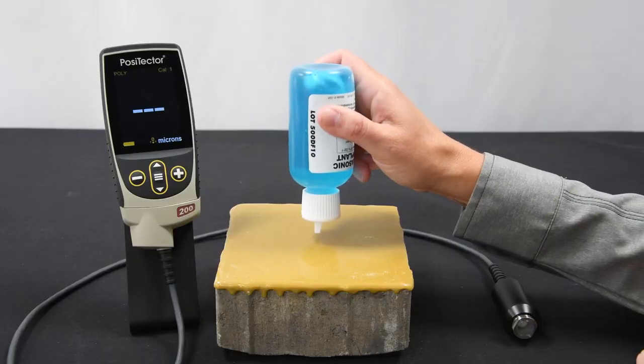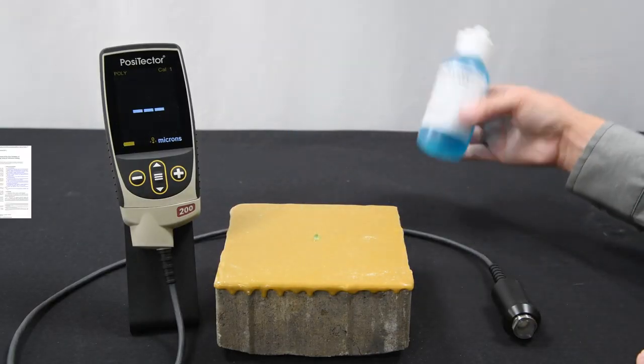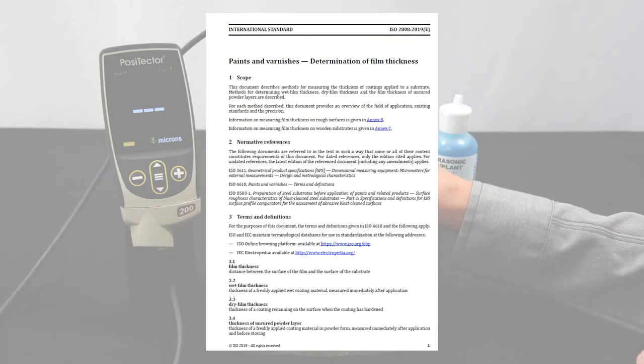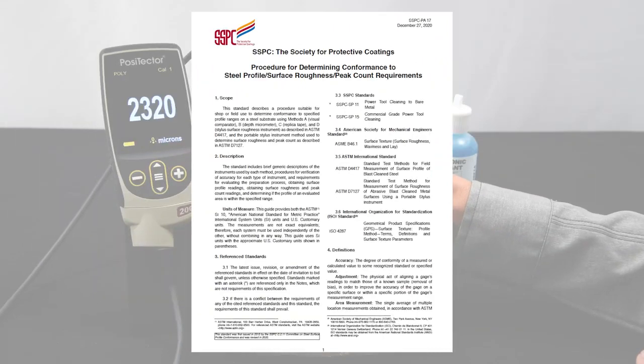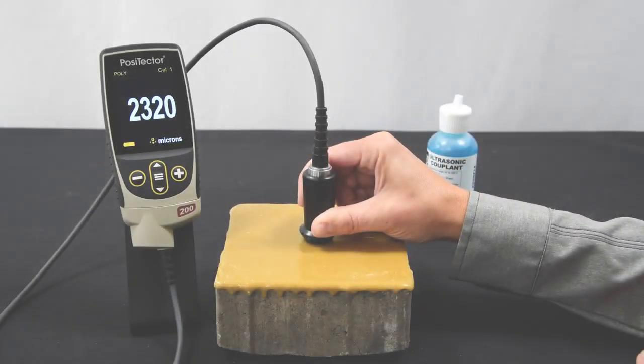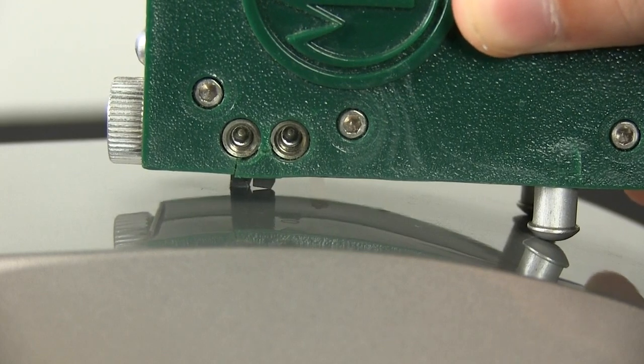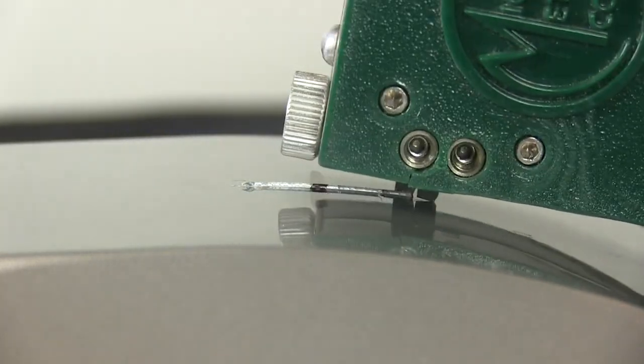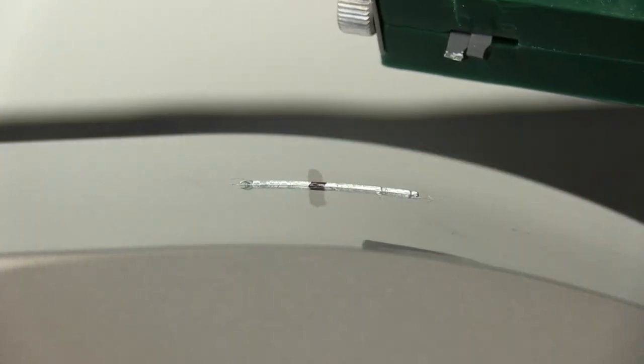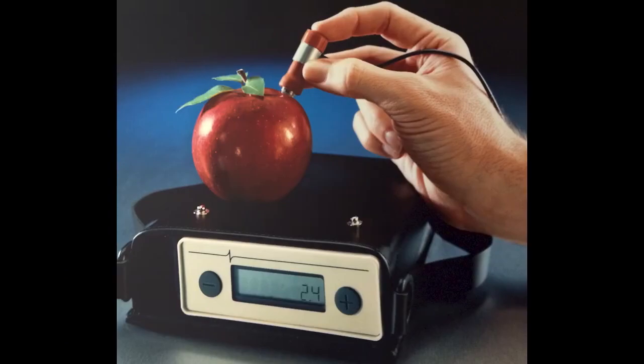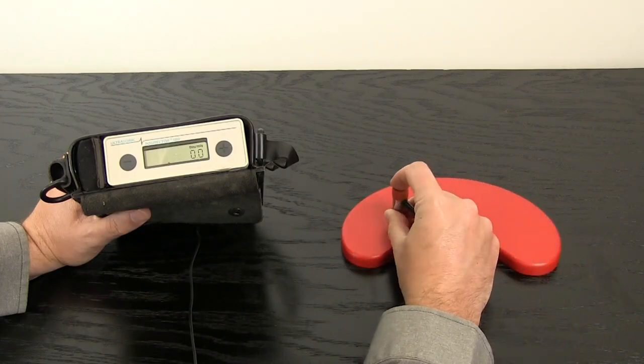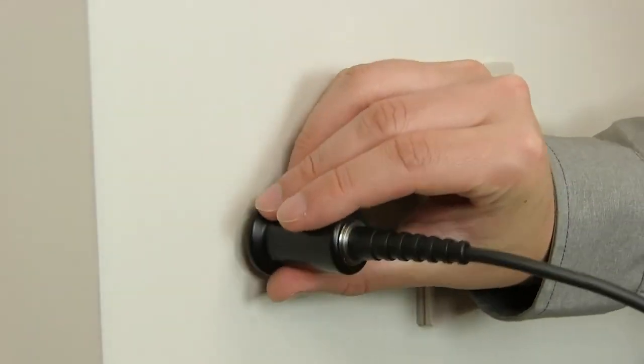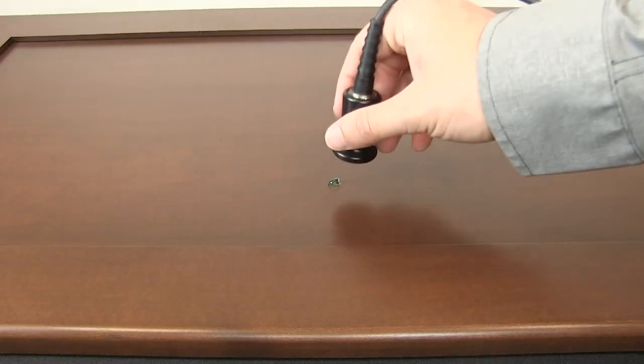The time-tested and proven non-destructive ultrasonic technique conforms to ASTM D6132, ISO 2808, and SSPC PA17, and is widely accepted by many international organizations. In the past, measuring coating thickness on non-metals such as wood, plastic, and concrete required destructive cross-sectioning methods. Everything changed in the early 90s with the introduction of the Positector 100, the first handheld ultrasonic coating thickness gauge.